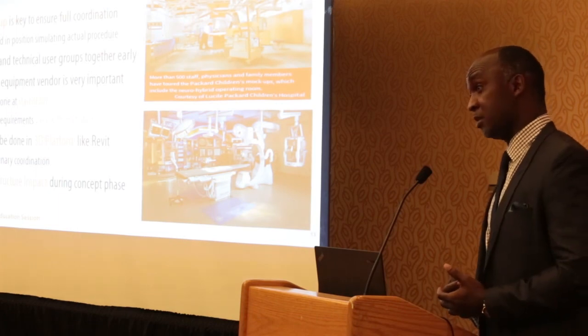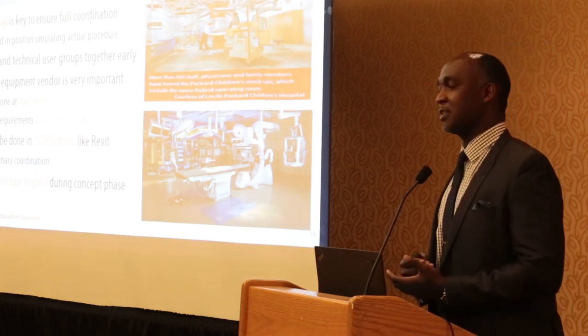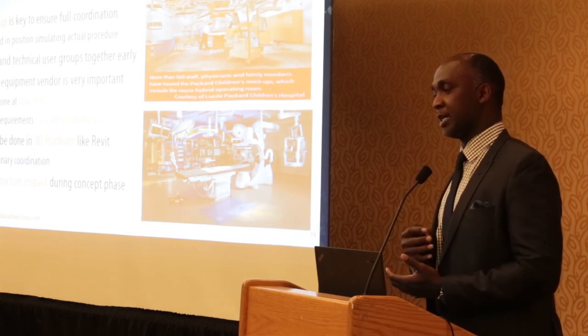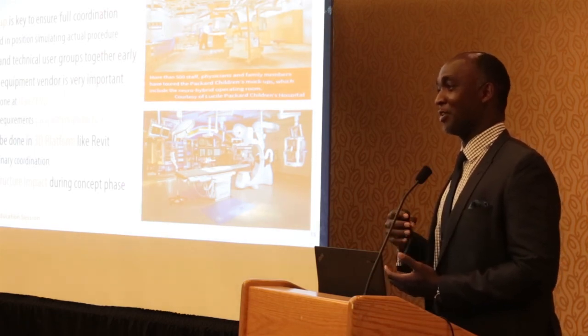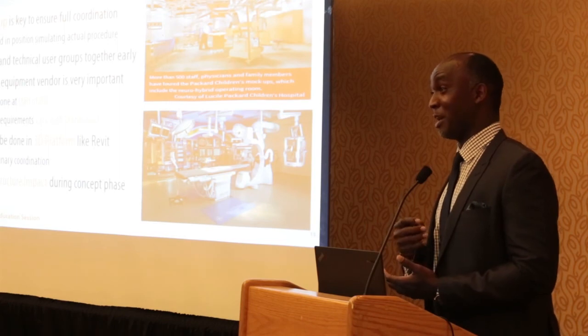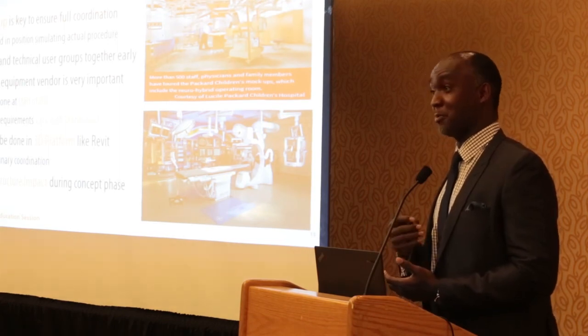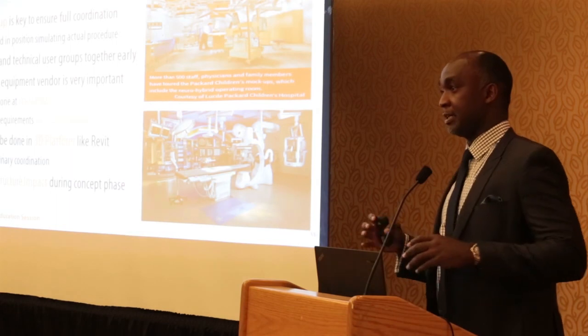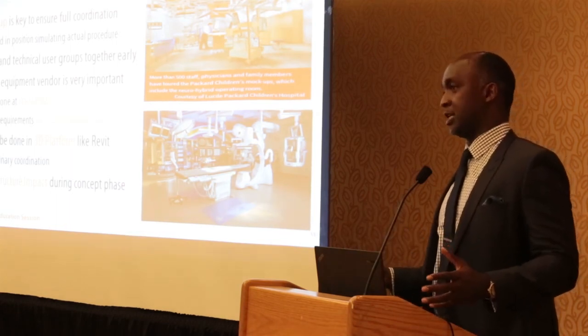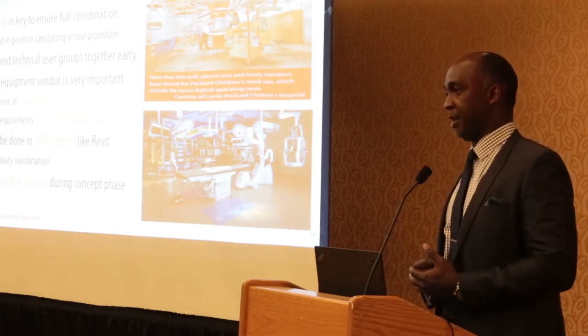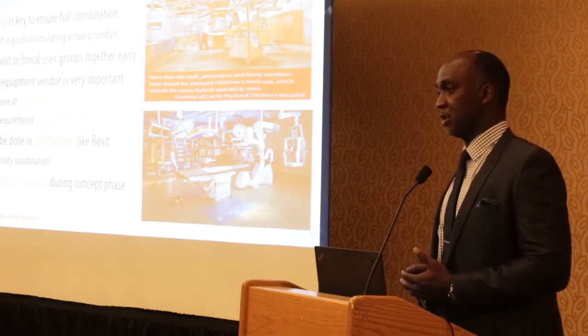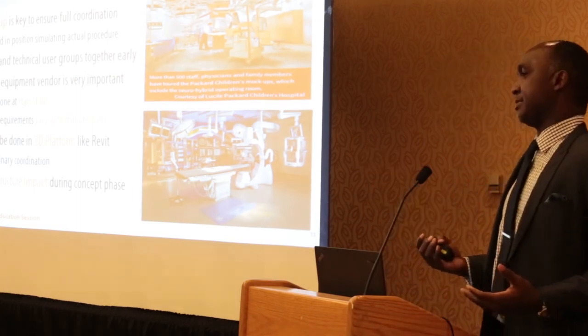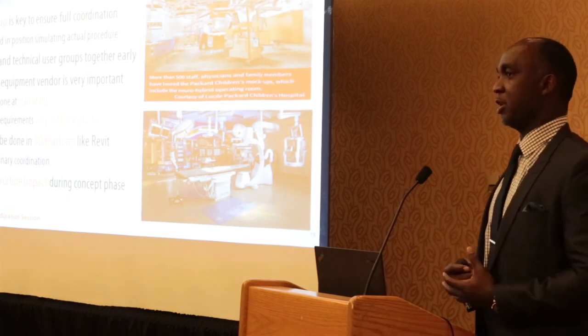Early decisions have to be made. The size of your space is extremely dependent on the type of imaging equipment and manufacturer you have. Siemens is very different from another manufacturer, and it's a fact of the segment. So you have to make sure you pin down your manufacturer as early as possible. I'd say by DD, but even in your concept, you should try to make sure you know and select your equipment way before you start designing.